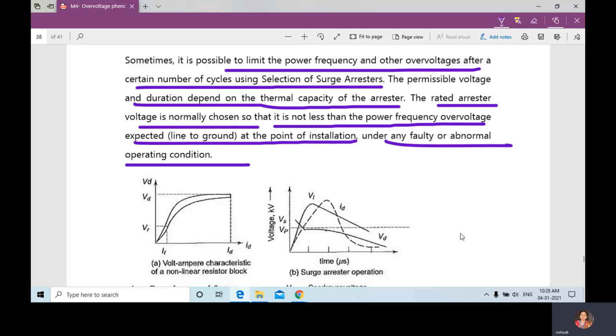They are saying that the rated arrestor voltage is normally chosen so that it is not less than the power frequency overvoltages expected, that is line to ground, at the point of what? At the point of installation. While installing, we should note that it should not be less than the power frequency overvoltage under any fault or abnormal operating conditions. We should know beforehand, if any fault occurs, how much voltage rise and how much overvoltage will occur. Depending on that only, we should select the voltage arrestor or surge arrestor.